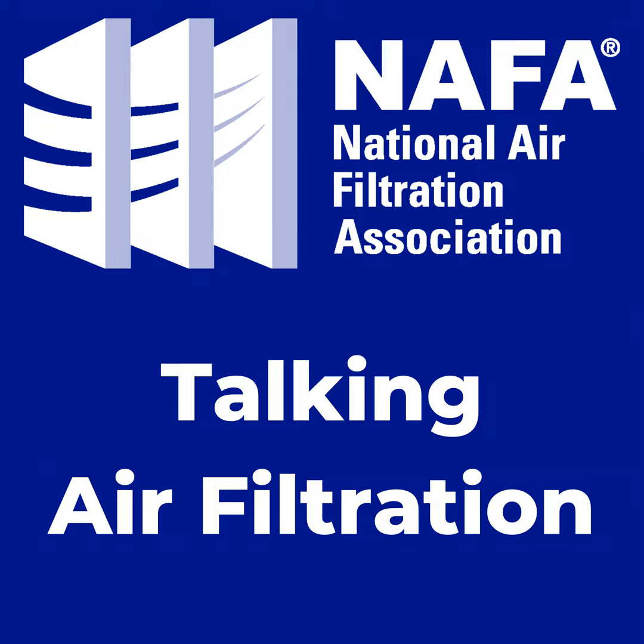And then, the future is also kind of what's going on now, which is how we improve lower efficiency media with nanofibers. Ignoring the dust load part that I talked about earlier, because I know that's kind of a function of poor test methods right now, and the ASHRAE dust not really being applicable to nanofiber medias. But you can take a MERV 7 media, so this media that we tested before and after nanofiber coating, and we boosted it up to a MERV 11. And you can see the pressure drop does go up by a factor of 2. You're doubling your pressure drop, but you're getting that efficiency performance that you're not getting.